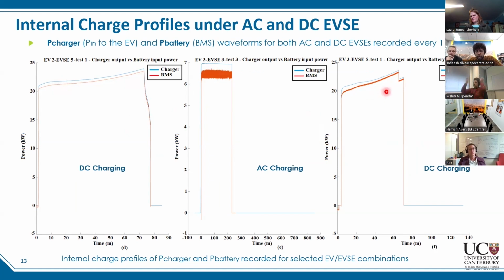EV2 and EV3, when connected to EVSE5, the 25 kilowatt Delta charger, had remarkable similarity in their charging patterns. The gap between the blue trace and the red trace is very minimum. Maybe a maximum of 1 to 2 kilowatts is used for battery thermal management, while the majority of power is allocated for battery charging. That's why the gap is very minimum between these two traces.